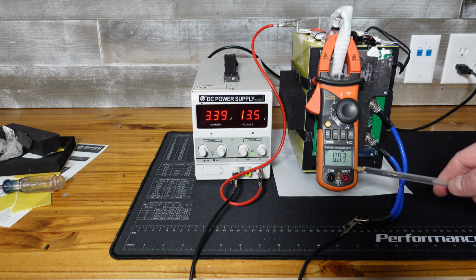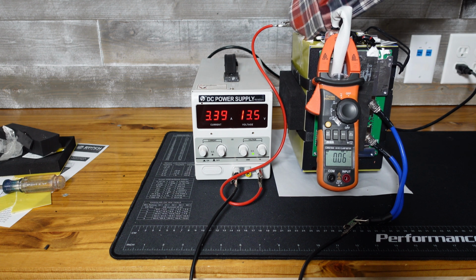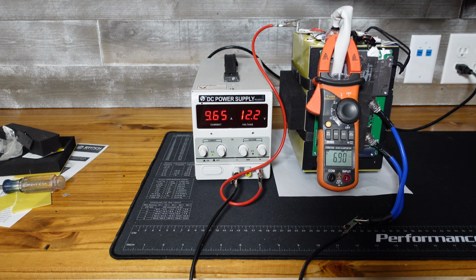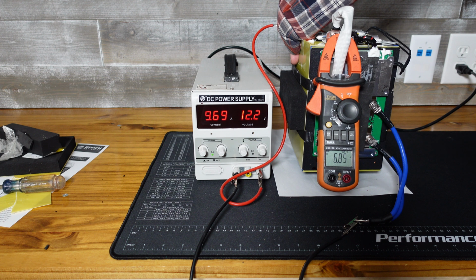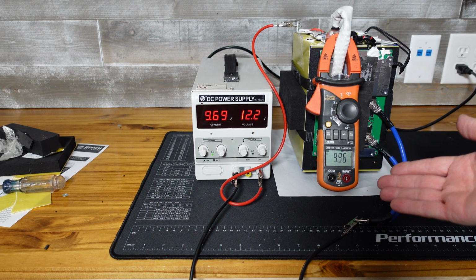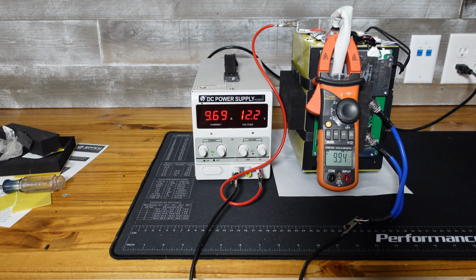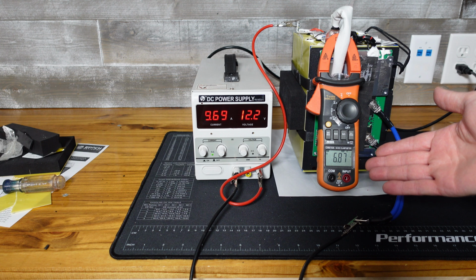As soon as that temperature sensor we sprayed warms back up, we should see this begin charging again. So let me try to warm that up artificially here. And there we go, we began charging again at 6.9 amps, so we know that heater is still on. It may need a little bit more warmth here. And we're back to 10 amps, so the heater has now shut off. So let's try that one more time just to be sure. The heater's on.